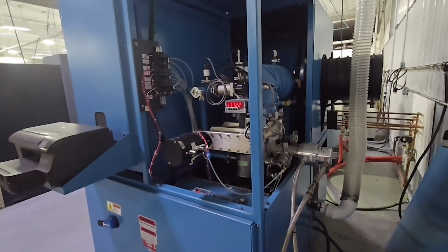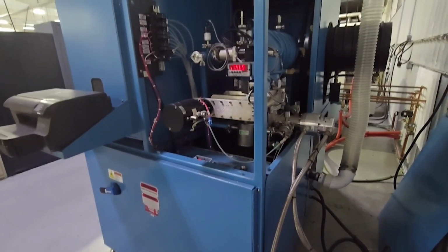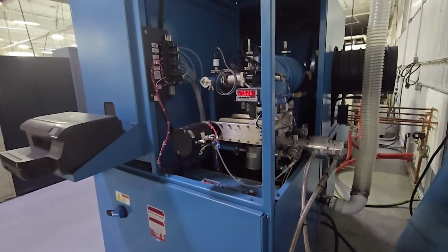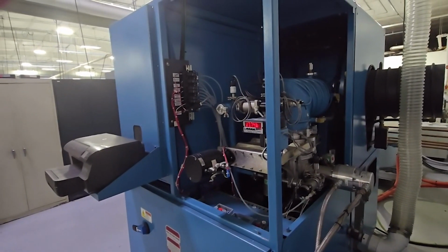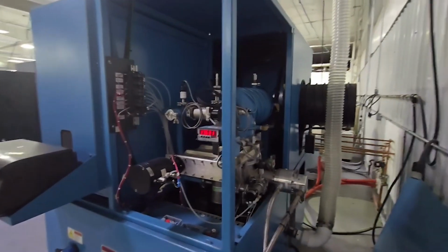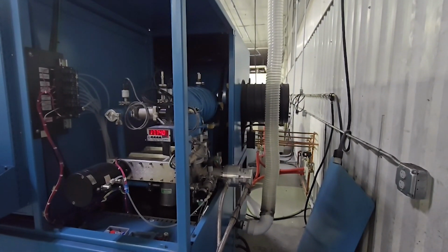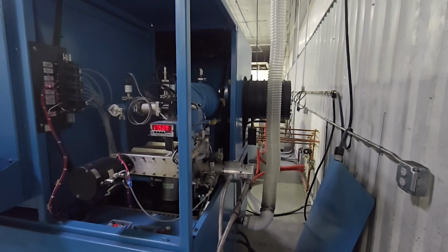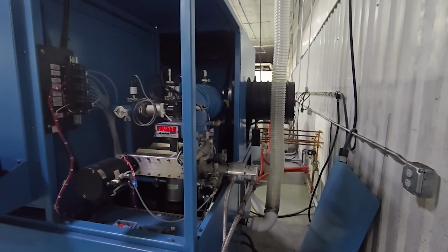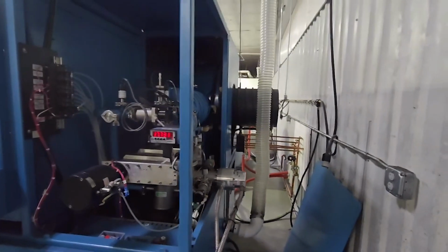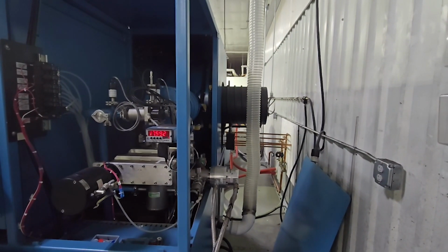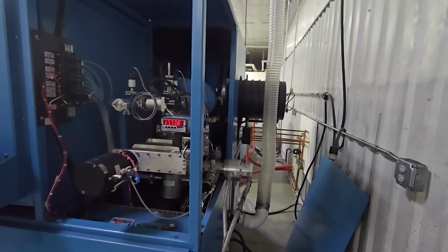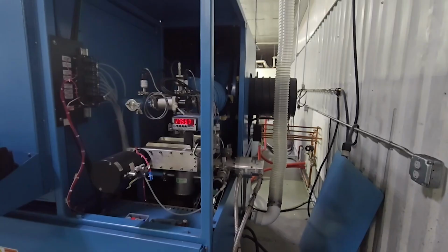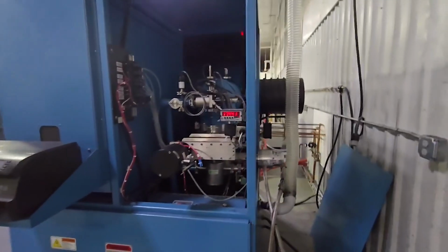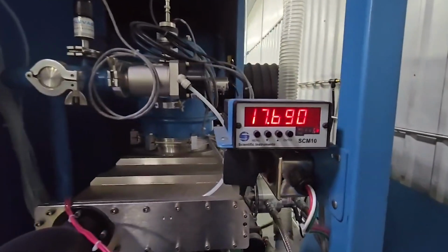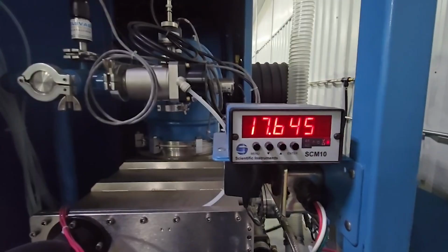Here's a back view of the vacuum brazing unit. You can see the 2 tubes coming into the cryo pump, and on the back side you can see the large blue entry into the vacuum chamber itself. We do have the machine vented to the exterior of the building. That's just to vent any residue, moisture, and gases that it expels. Behind that tubing, you can see a large black colored cylinder on the back of the machine. That's actually an internal cooling fan, and that can be used as well to assist the cooling of the machine. The digital readout that you're seeing right there is actually reading the temperature of the cryo unit. It's right now right around 17.5.